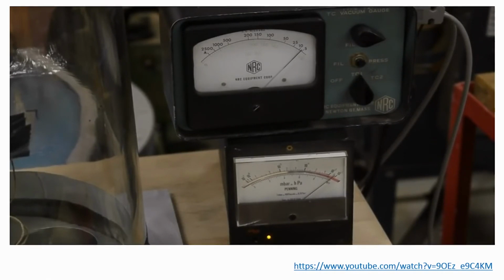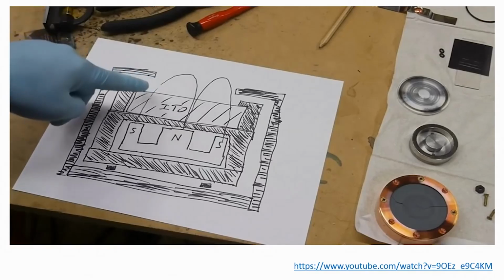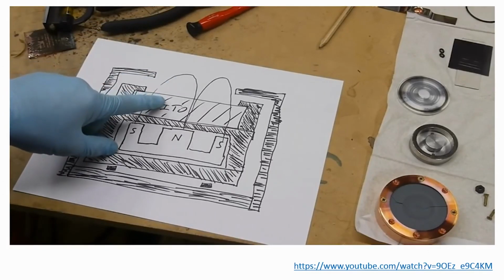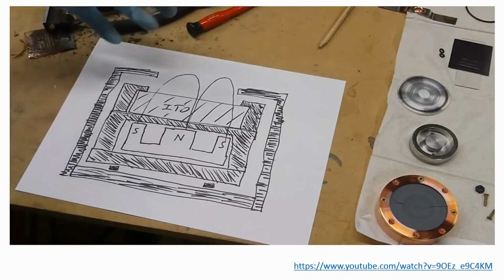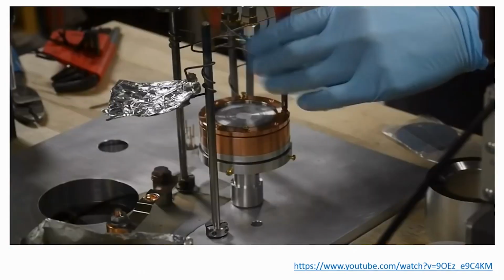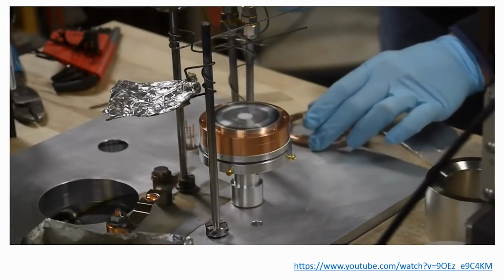However, the high pressure is such a good conductor because there's so many ions, it's tough to get the voltage high enough so that the incoming ions are going fast enough to cause the sputtering to happen. You'll have a nice glow discharge and things will look like they're working, but you just can't get the voltage high enough without blowing everything up basically.